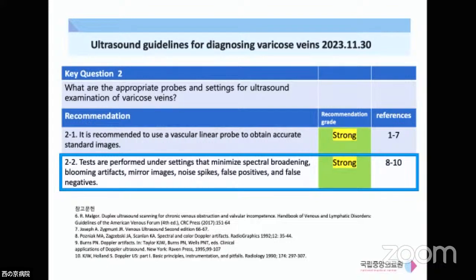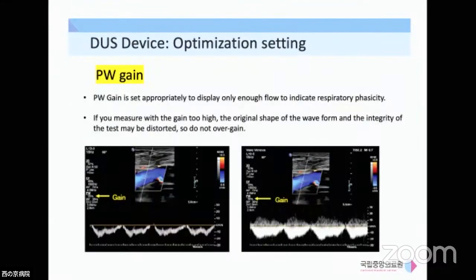Number 2, testing performed under settings that minimize artifacts. About ultrasound optimization, PW gain is set appropriately to display only enough flow to indicate respiratory phasicity. If you measure with the gain too high, the original shape of the waveform and the integrity of the test may be distorted.